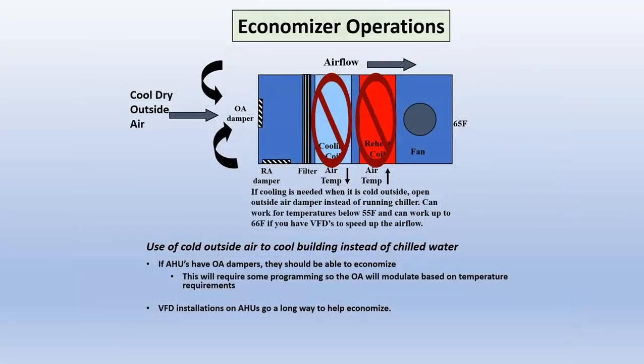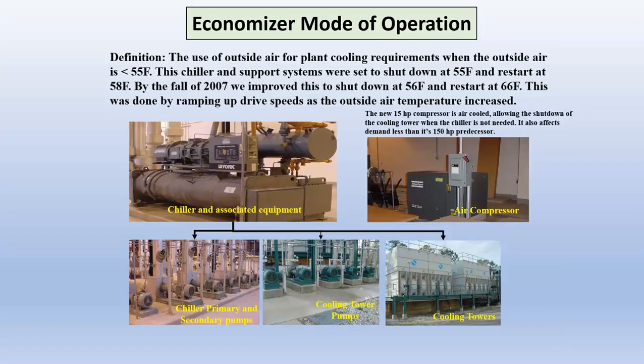Basically, here's a slide that shows Economizer Operations. Instead of using the cooling coil and a reheat coil and all that, I'm just going to use outdoor air and pump it through the air handler. Now, you can also use what's called a wet economizer, and that uses a heat exchanger and just wipes out the chiller and uses outdoor air to cool the chilled water via a heat exchanger. Those aren't as common, probably more expensive, a bigger pain. You've got to worry about freezing it more and stuff like that. Now, this is the kind of equipment that you can see get knocked out because of economizer. All this big equipment. I mean, you can really save a lot of money by using it. And we were able to get our economizing window all the way up to 66 by playing around with the drives.